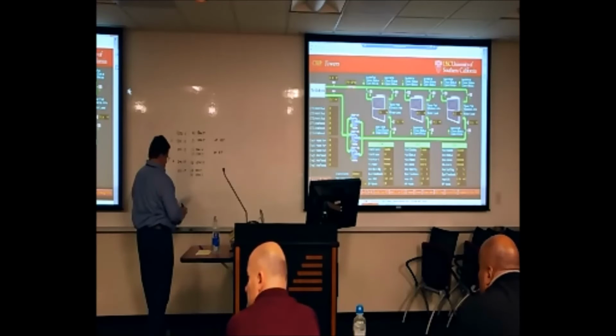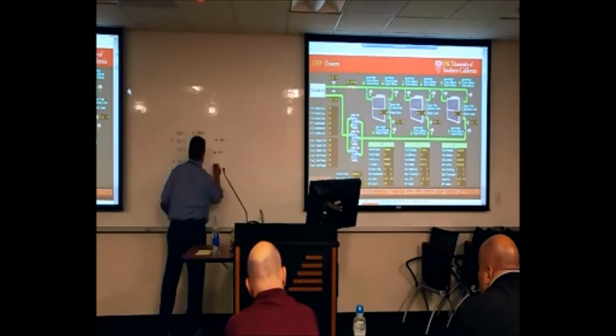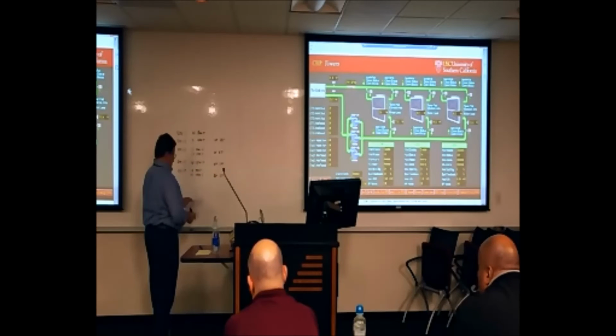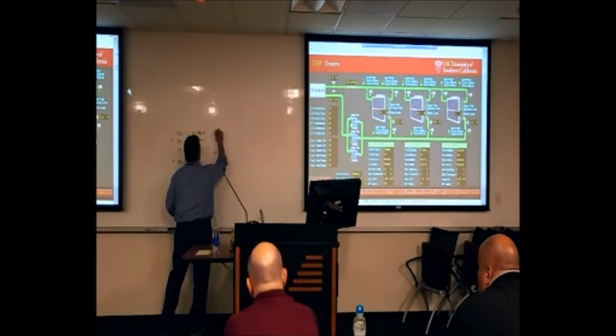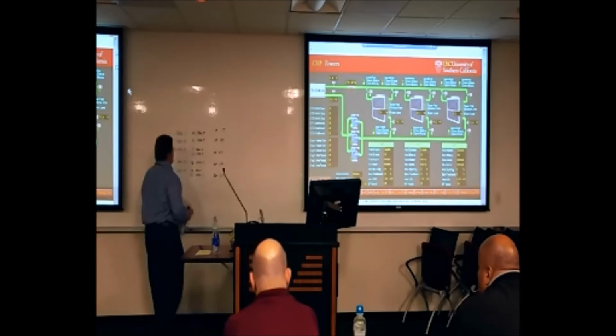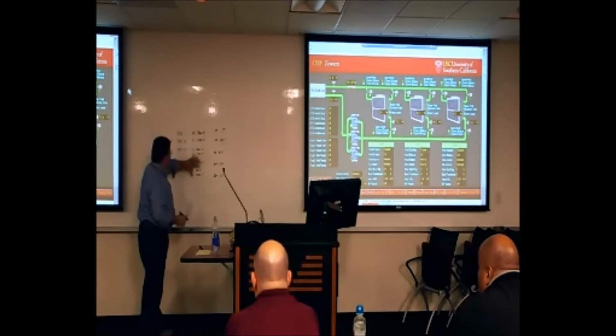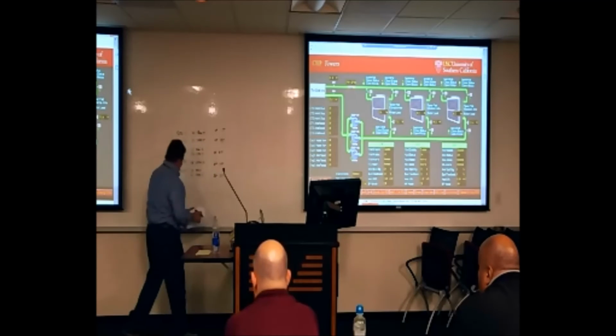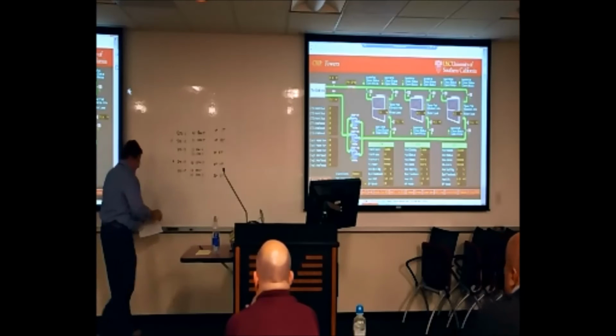And then stage 4, 2 pumps and 3 towers. Stage 5 is 3 pumps, 3 towers. And stage 1 was going to be 1 tower and 1 pump. So that's how the equipment is staged. I've got the staging, I've got the chillers, I forgot to mention the equipment that's running with it, so there we go.